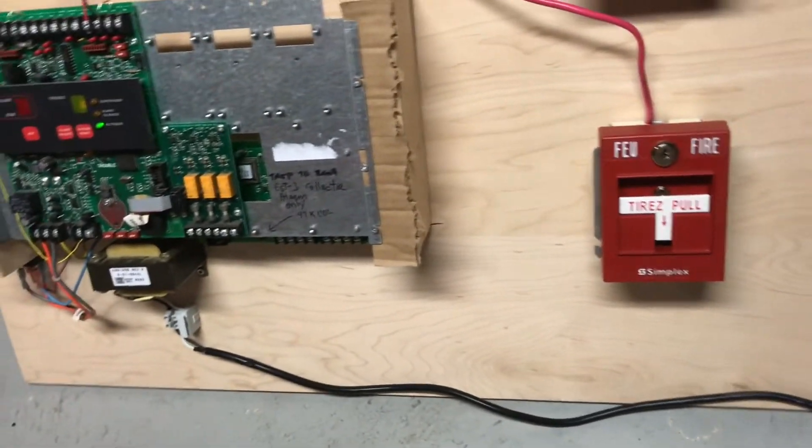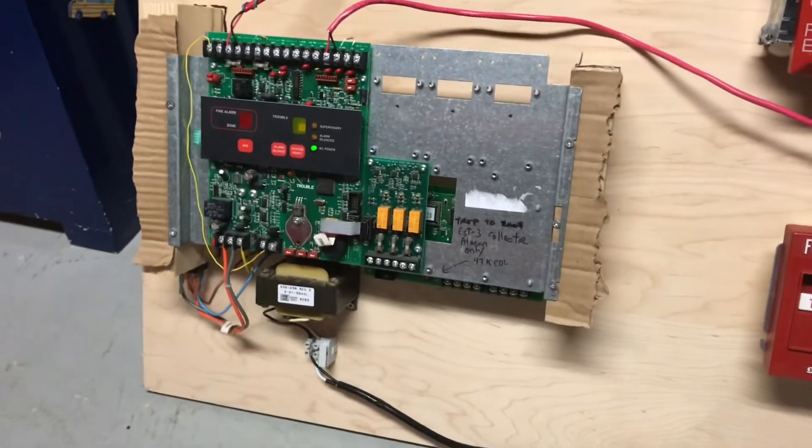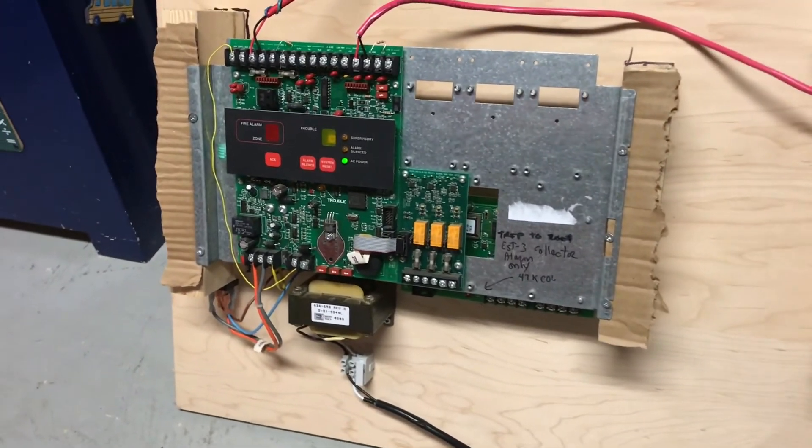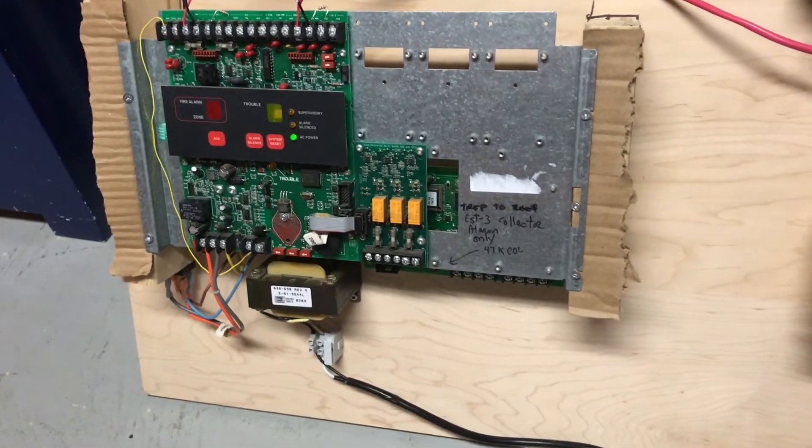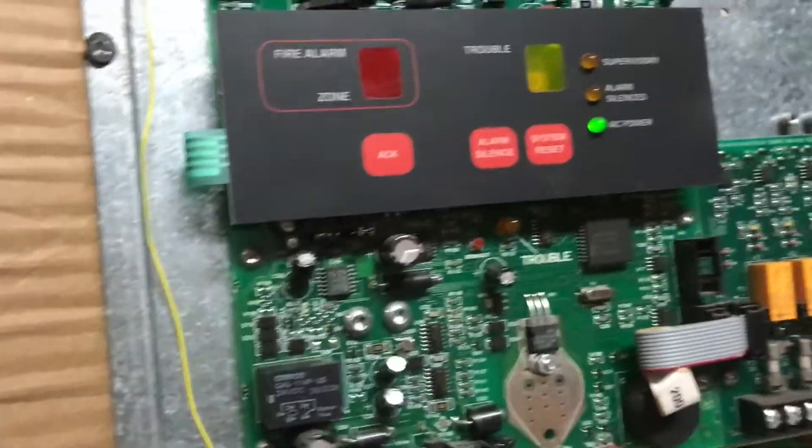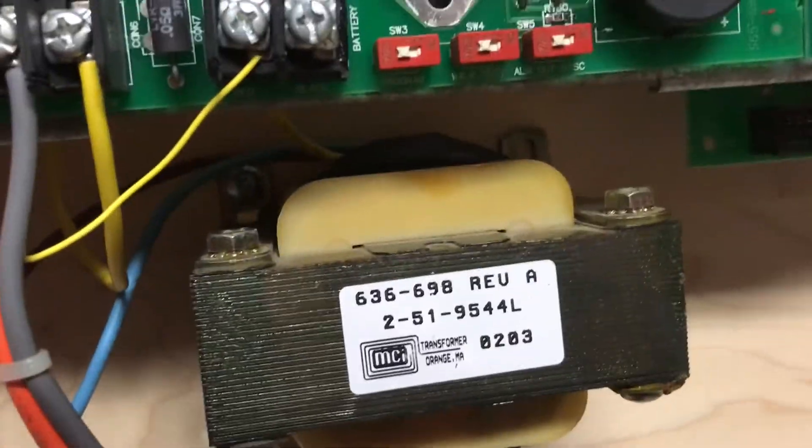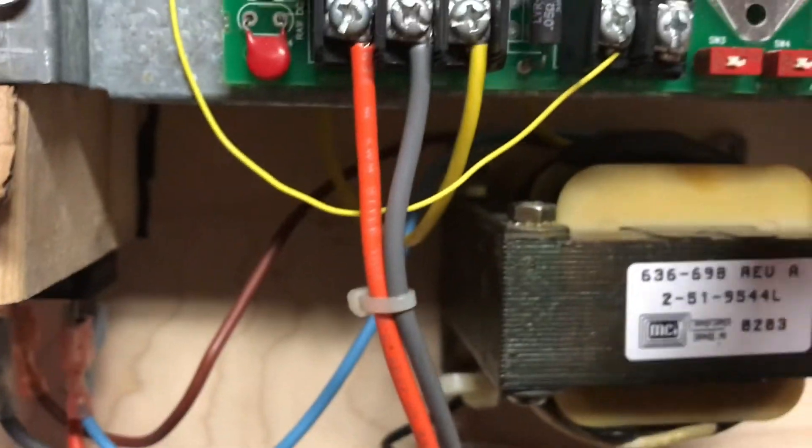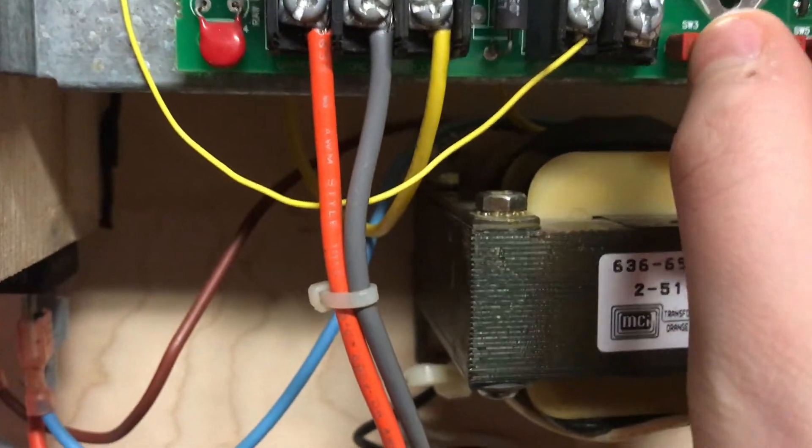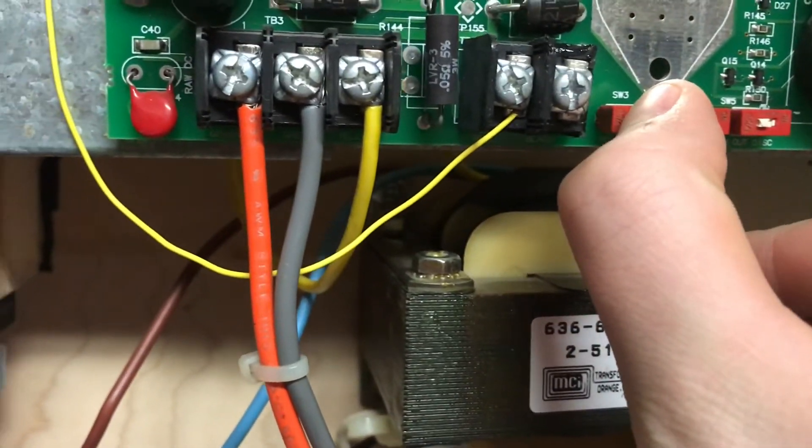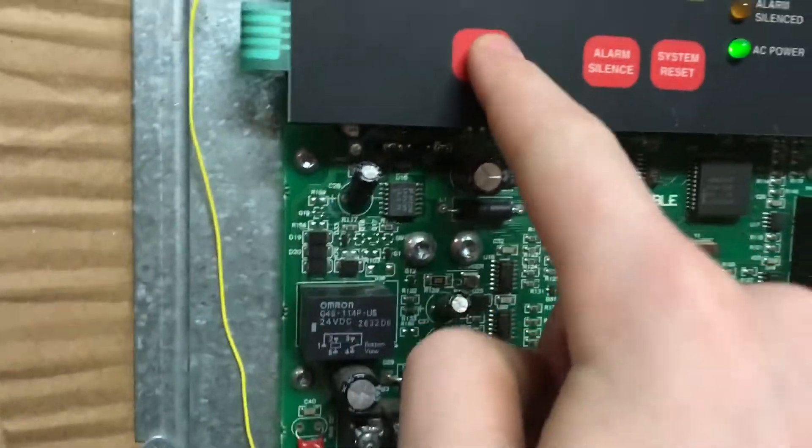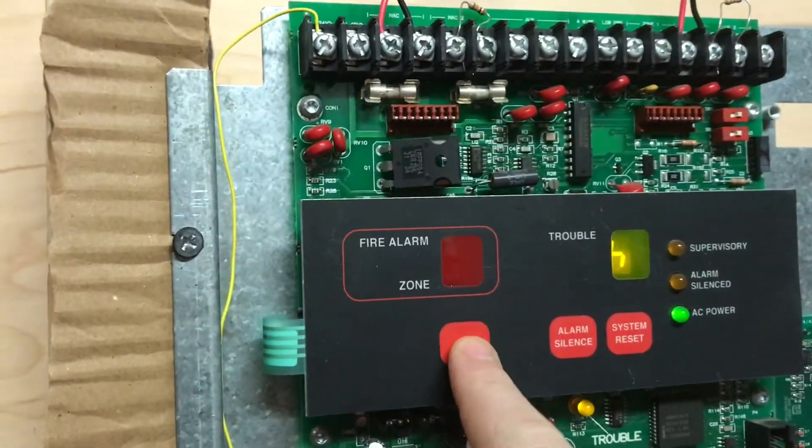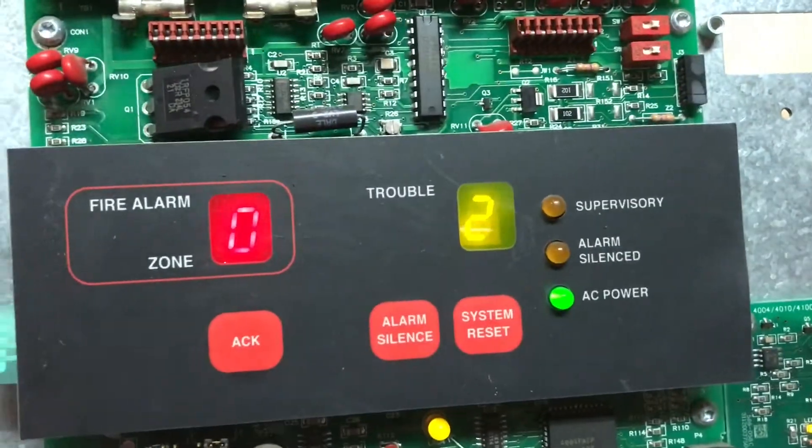I am going to go get a manual, because I still don't really remember all the programming options. We'll go into a little bit of programming and walk test. So first off, to put the panel into programming mode, we have to set SW3 to the on position. And you press ACK. And that brings up the options here.